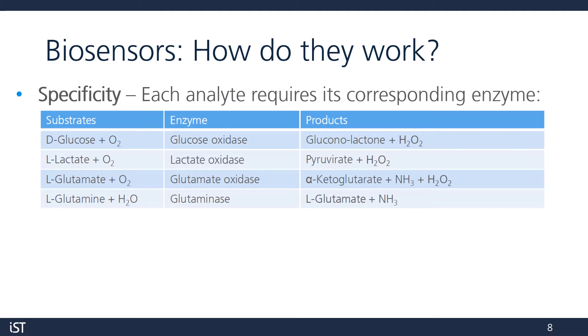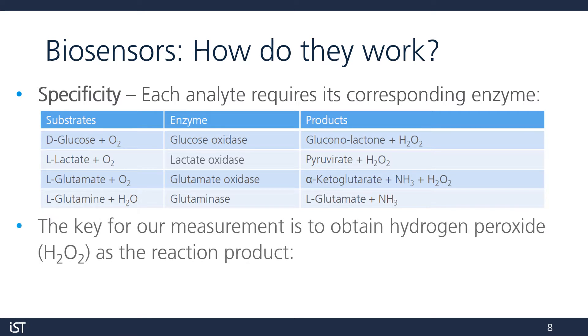Each of them requires a different enzyme for the appropriate reaction to take place: glucose oxidase for glucose, lactate oxidase for lactate, glutamate oxidase for glutamate, and glutaminase for glutamine. The key for our measurement is to obtain hydrogen peroxide, or H2O2, as one of the reaction products. We'll explain this a little more in the next two slides.